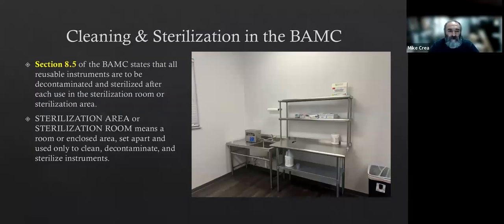Section 8.5 of the Body Art Model Code states that all reusable instruments are to be decontaminated and sterilized after each use in a sterilization room or sterilization area. Furthermore, it goes on to define a sterilization area as a room or enclosed area set apart and used only to clean, decontaminate, and sterilize instruments. So this should be a separate room in the facility where all they're doing in this room and at this sink is cleaning and prepping instruments to be put into the autoclave for sterilization. It's not a hand washing sink. It's not a tattoo artist sink. It's not your bathroom sink. It is a sink away from pedestrian access that is only used for the purposes of prepping tools and cleaning them prior to sterilization.